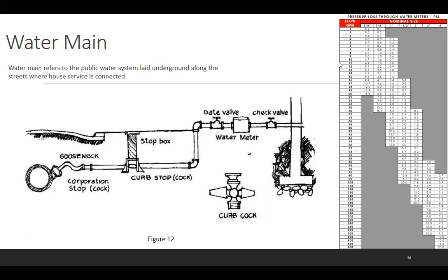So, dito kailangan nyo itong pressure loss to water meter. Kung gagamitin nyo ito pag ng pressure drop, kasi kung may pump ka dito, yung pump system mo dyan, kasama yan. Gate valve, pressure drop ng gate valve, saka sa check valve, plus yung water meter. Water meter, wala sa table natin doon sa plumbing code. So provide na lang tayo ng water meter pressure drop. Minimum is 3/4.